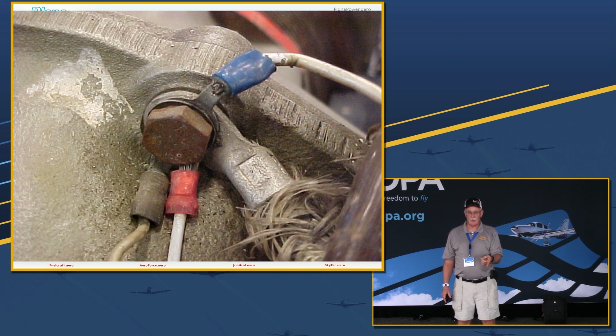Okay, this is grounding - look at this one. Is that a good ground? You can't tell me that's sitting there fine, you don't have a clue. It may be perfect, but when I look at it, I see a heavy cable with the old cloth braid on it that's coming apart. That tells me that cable is no longer protected, which tells me moisture and anything else has penetrated it, which means you may have a high resistance connection right there at that terminal.